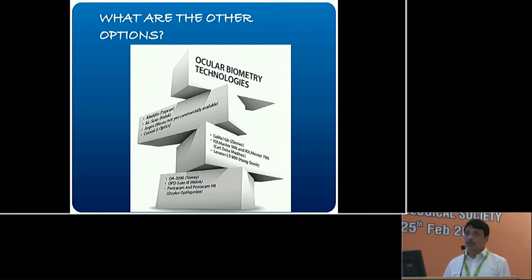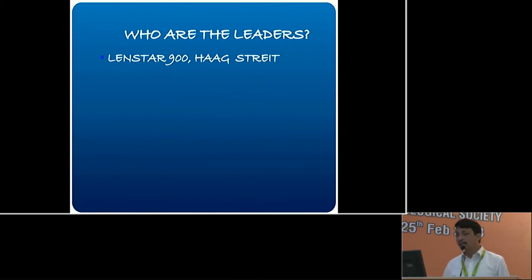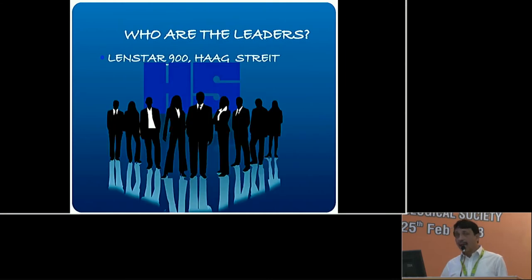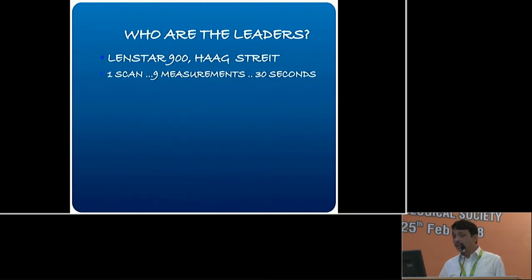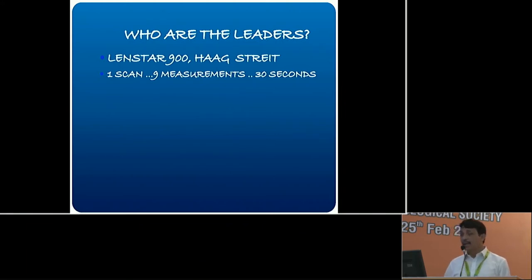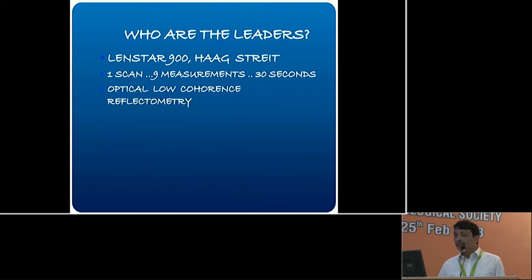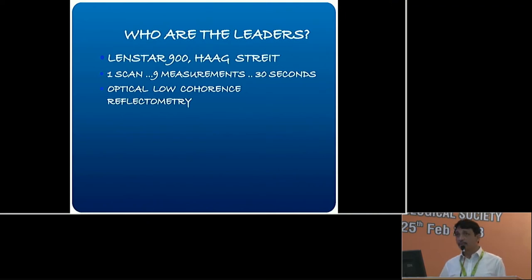Which one should you choose? Let's look at the leaders. Ten years after the IOL Master was launched — in 2009 — Haag-Streit launched the Lenstar 900. It does one scan in 30 seconds with nine measurements and is doing very well nowadays. It uses a slightly different principle called optical low-coherence reflectometry — similar to but not identical to the IOL Master's principle, but equally effective.